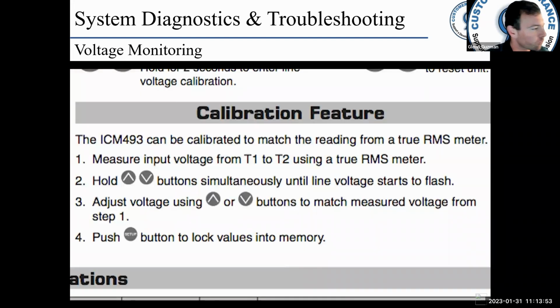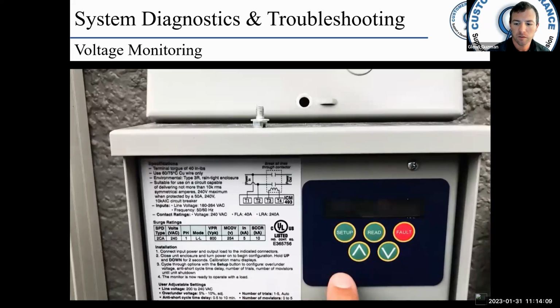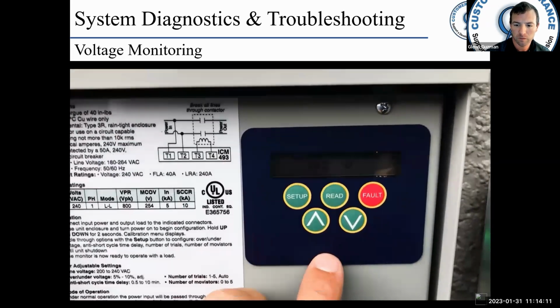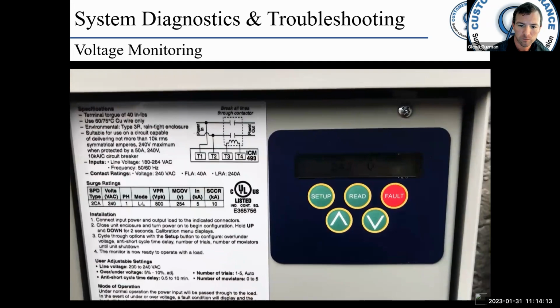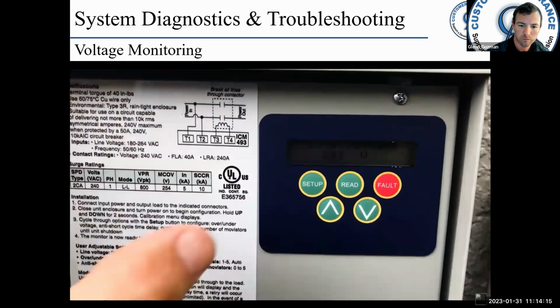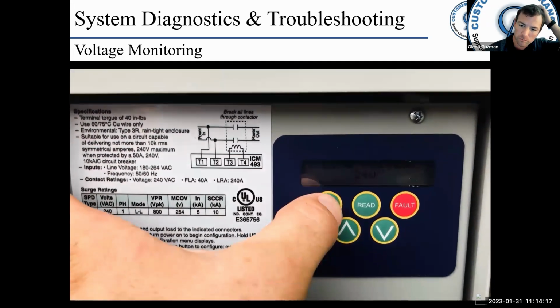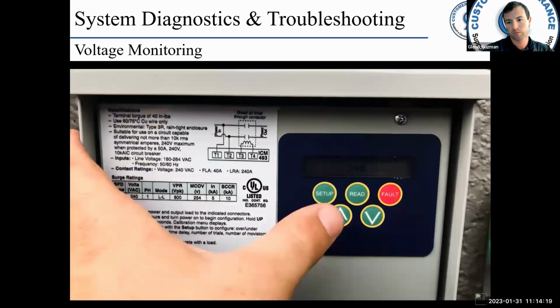The last step is actually calibrating the ICM 493. How you're going to do this is push the up and down arrows until your line voltage starts to flash. And with an RMS meter, you're going to check your line voltage between L1 and L2. Go up and down as required. This one's already dialed in at 242 volts. Once you've got it dialed in, you just push the setup button and you are good to go.